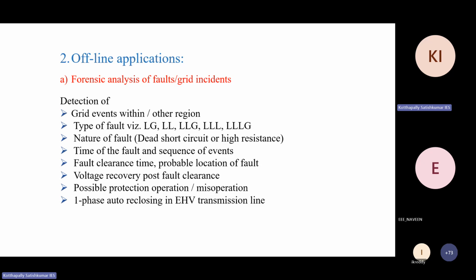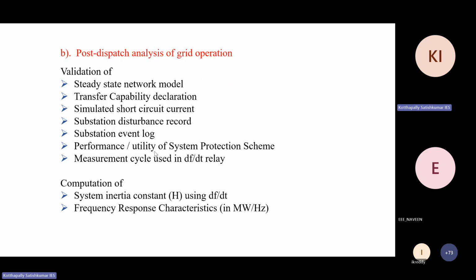You can easily tell because the time is so accurate, in the range of microseconds and milliseconds. You can tell easily from where this fault started. And also fault clearance time, probable location of fault, voltage recovery post fault clearance, and possible protection operations and misoperations. Single phase auto reclosing in EHV transmission you can also observe, because it is in the range of milliseconds and microseconds. You can go through these offline applications.